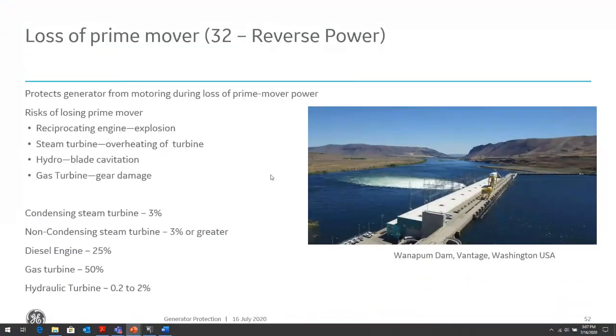So, the power loss of prime mover. What happens when we lose a prime mover? The generator becomes a motor, we have a motoring condition now. So we want to be able to prevent motoring conditions on the loss of the prime mover. Damage can be heavy depending on the type of machine. Heavy steam turbines can have a lot of overheating in the turbine, which can cause issues with the turbine, can cause explosions, can cause catastrophic damage.